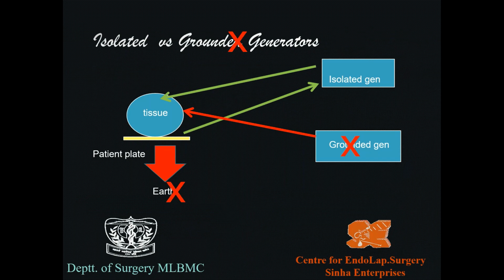Now, I told you about the isolated and grounded generator. Let's see what happened initially when the electrosurgical unit was designed for the first time. The current used to come from the generator to the tissue. It never went back to the generator. Where did it go? From this plate underneath the patient, it went to the earth. So at that time it was known as the earth plate, and this was known as a grounded generator. Why grounded generator? Because the generator was generating a current which was going to the ground. So grounded generator, no longer used. That's why the big crosses. So no earth plate, no grounded generator.